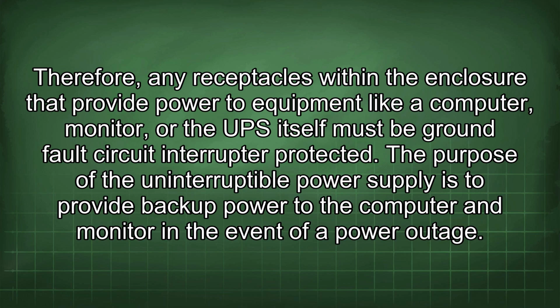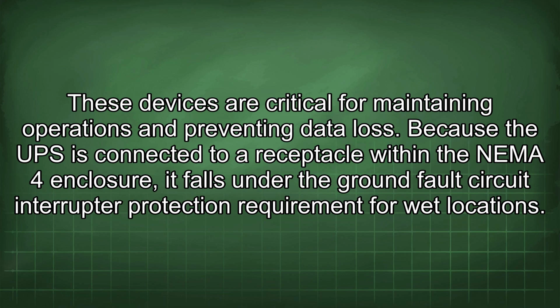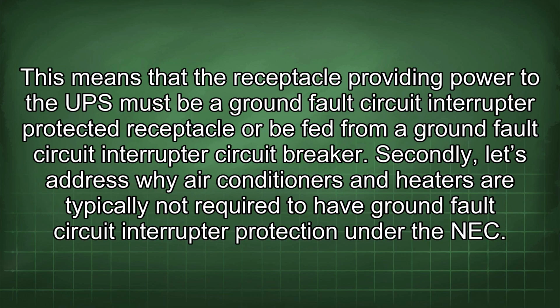The purpose of the uninterruptible power supply is to provide backup power to the computer and monitor in the event of a power outage. These devices are critical for maintaining operations and preventing data loss. Because the UPS is connected to a receptacle within the NEMA 4 enclosure, it falls under the ground fault circuit interrupter protection requirement for wet locations. This means that the receptacle providing power to the UPS must be a ground fault circuit interrupter protected receptacle or be fed from a ground fault circuit interrupter circuit breaker.